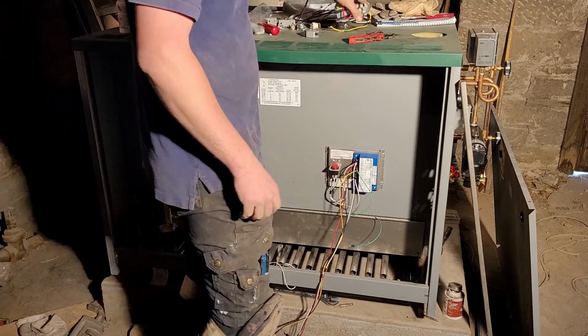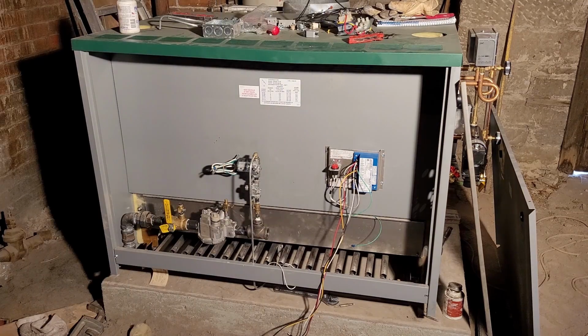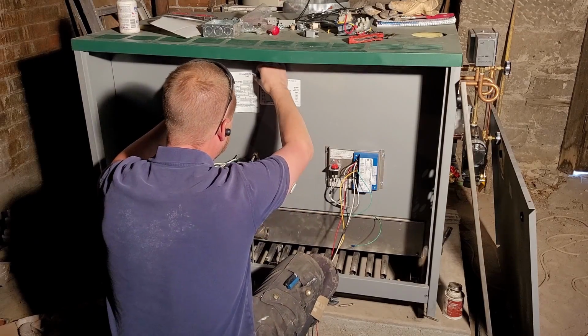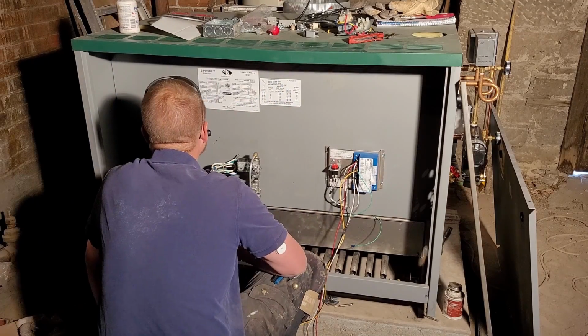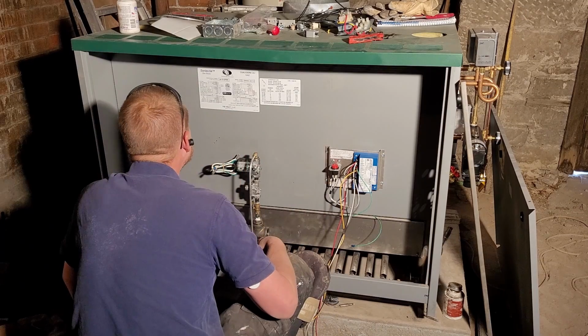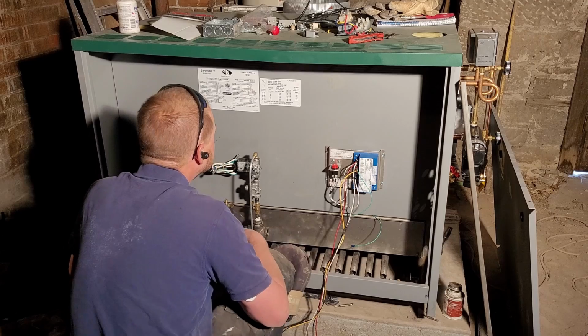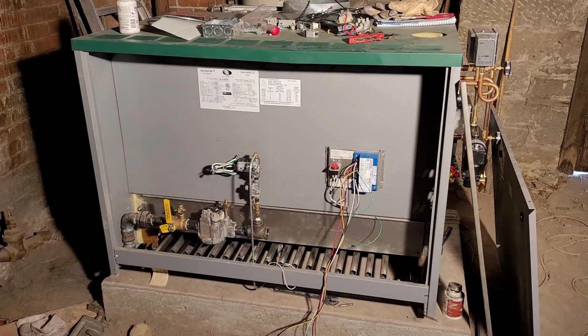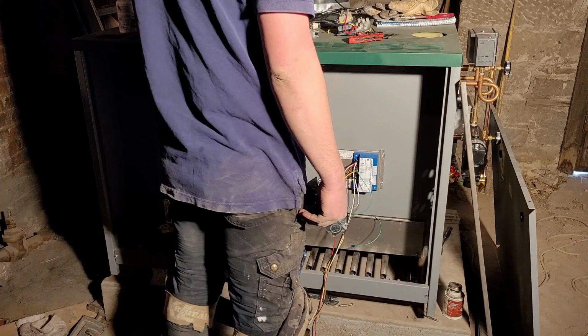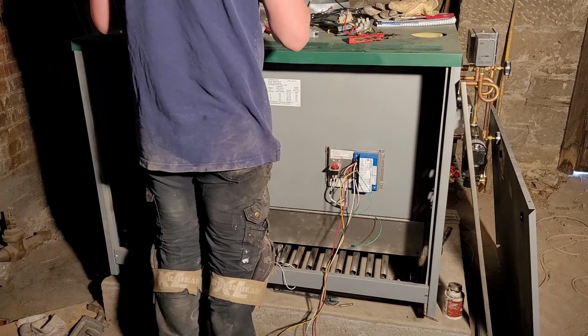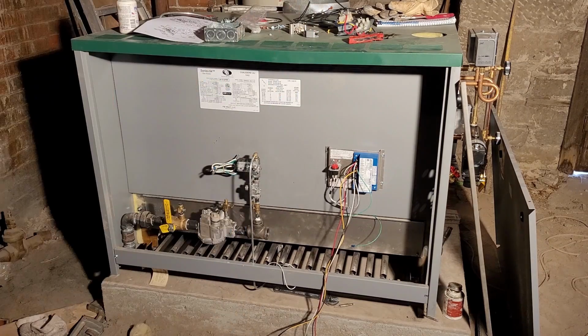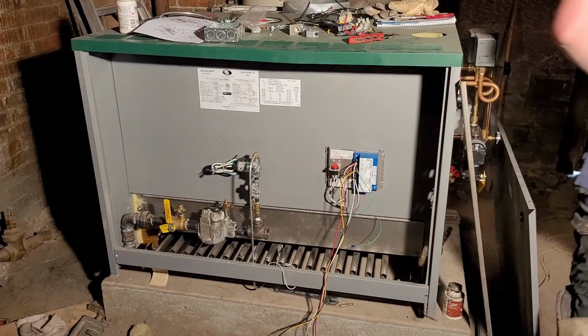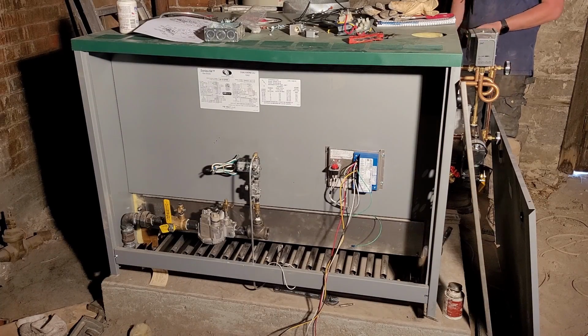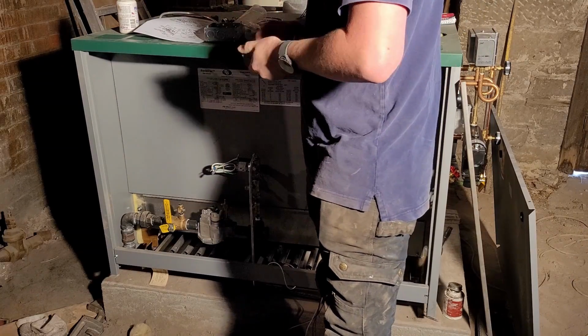So now we use what are called ionization probes. This is a little tiny probe that sits in the pilot flame, just like a thermocouple would, but it's not relying on the probe itself generating any current. It's actually using the pilot flame itself. I know that sounded weird, but fire is nothing more than very hot ionized gas. And because it is ionized, there's a lot of free electrons in that pilot flame, and you can actually pass current through the flame. Now, very, very high resistance, and there's a very small current that you can pass through it, but you can still do it.